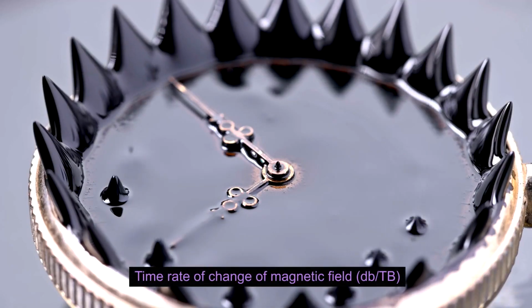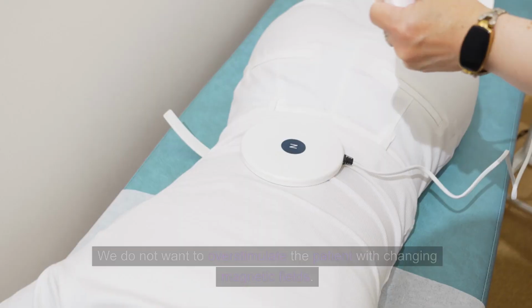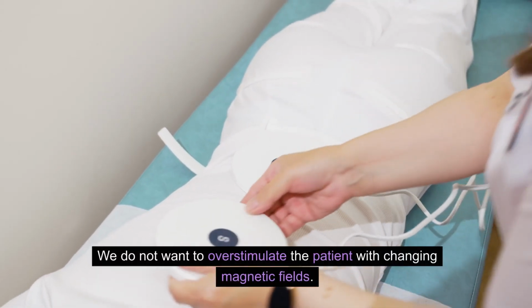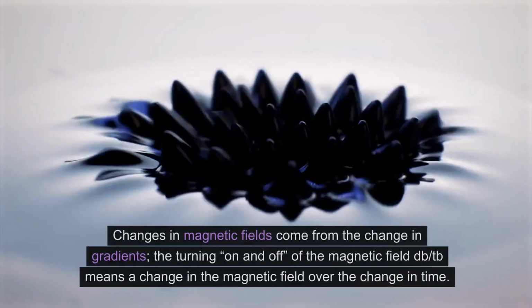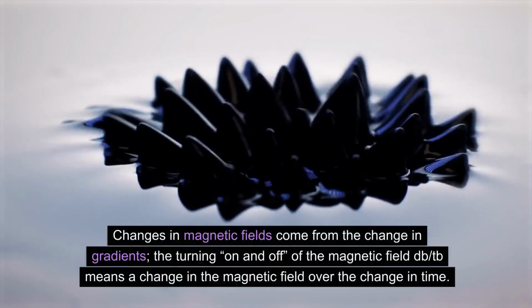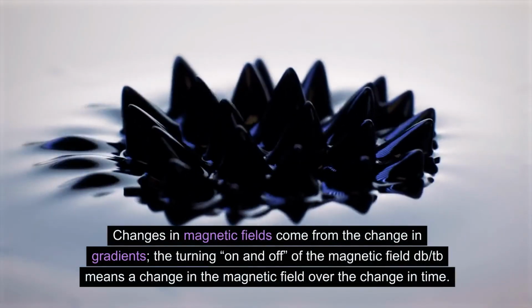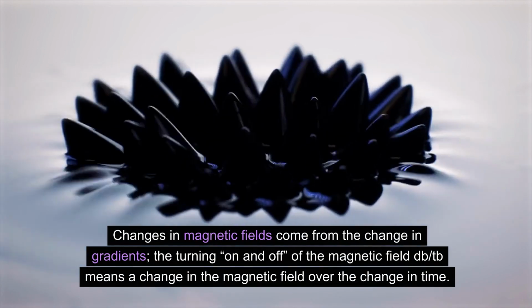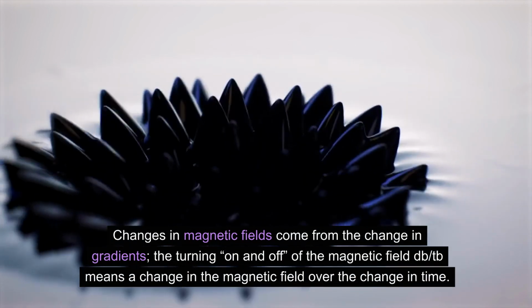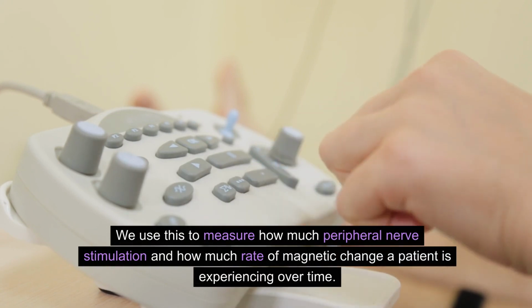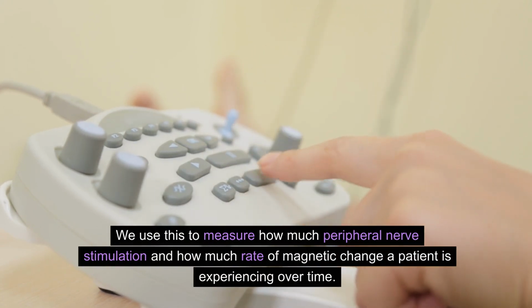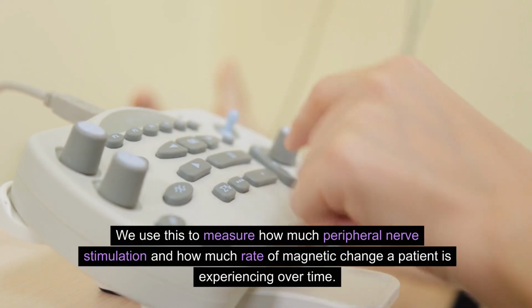Time rate of change of magnetic field, dB/dt. We do not want to overstimulate the patient with changing magnetic fields. Changes in magnetic fields come from the change in gradients, the turning on and off of the magnetic field. dB/dt means a change in the magnetic field over the change in time. We use this to measure how much peripheral nerve stimulation, and how much rate of magnetic change, a patient is experiencing over time.